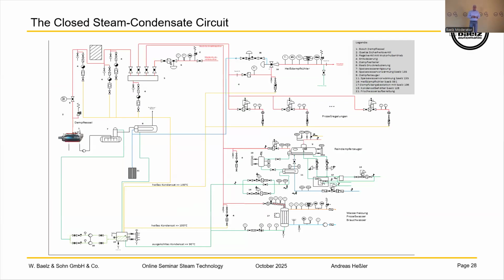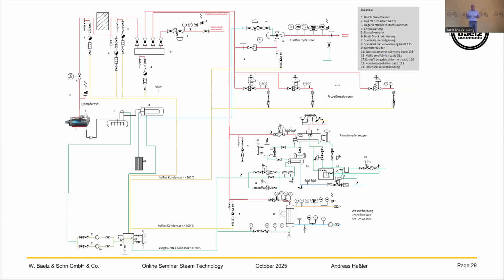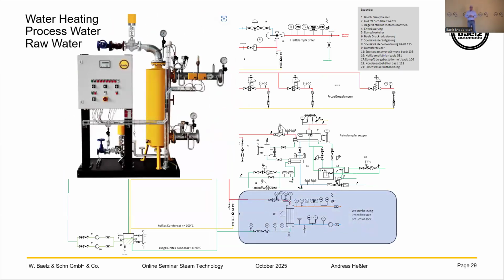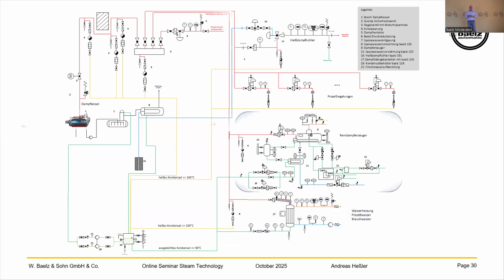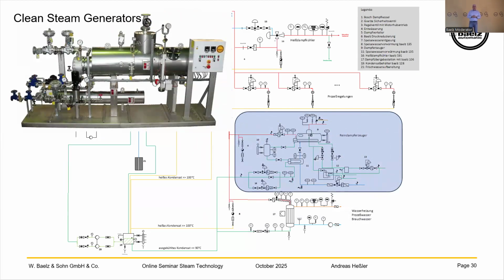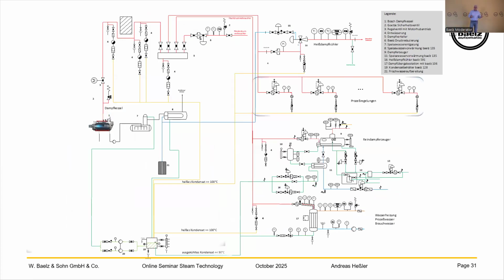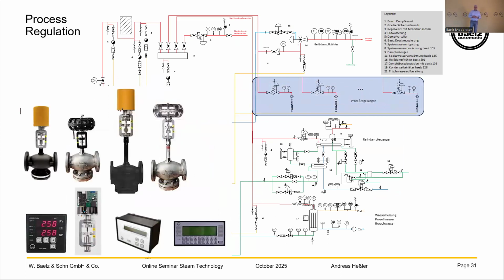On the next slide we see a schematic of a closed steam condensate circuit. I want to show you where we are. I chose this because a closed condensate circuit is very normal for BAELZ. We start here with water heating, process water and raw water heating, where we use our heat exchanger. The next one is our clean steam generators, used in this circuit. Then, of course, you need some control valves in this circuit. We have the regulators for them, and different kinds of actuators, like Michael already told you. So you can use all of our control valves with the controlling and measuring.